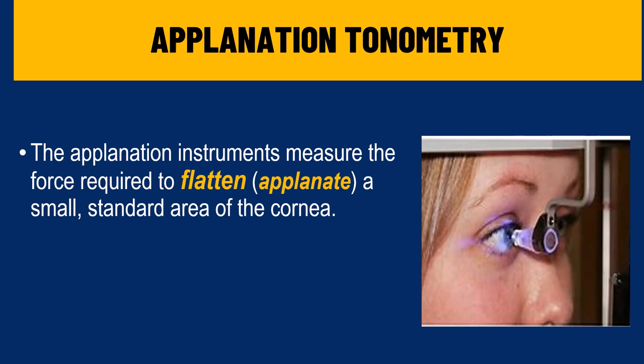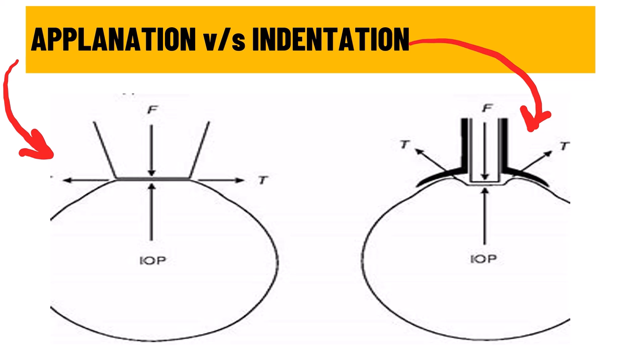The applanation tonometer basically measures the force required to flatten a small standard area on the cornea. The term applanation means creating a flattening effect on the cornea using some amount of force. In indentation, as the name suggests, we were creating a dent or depression inside the cornea using a specific force of the tonometer, specifically the Schiotz tonometer, and based on the force applied we were calculating the intraocular pressure.